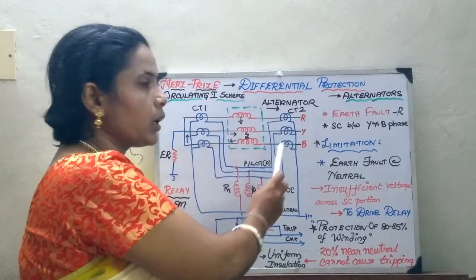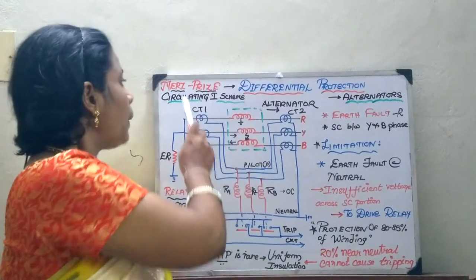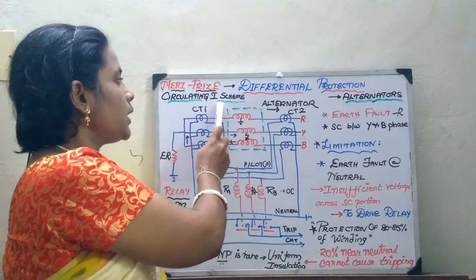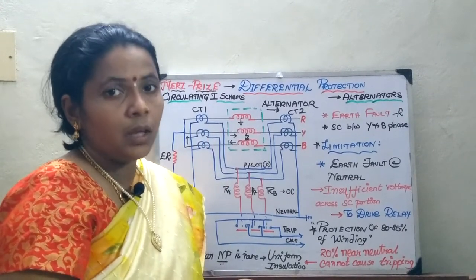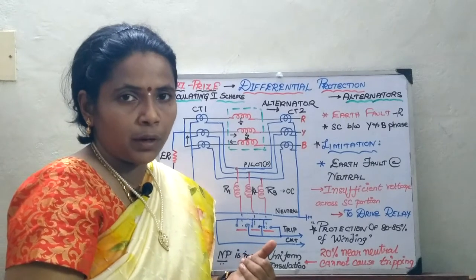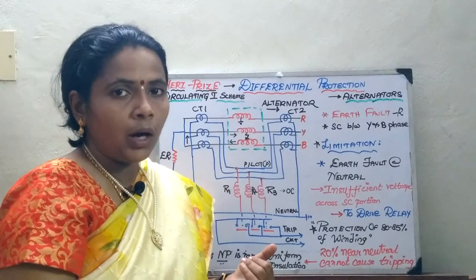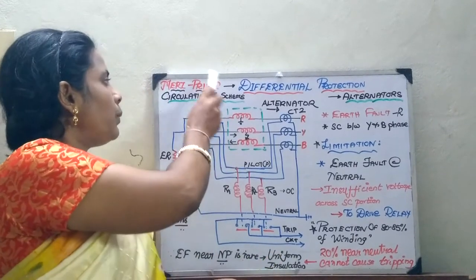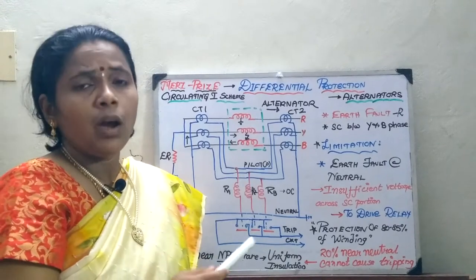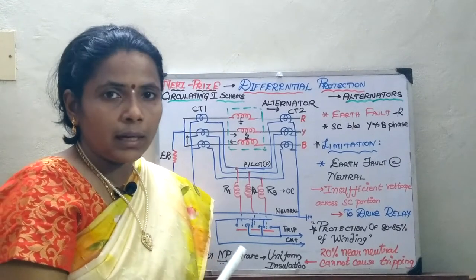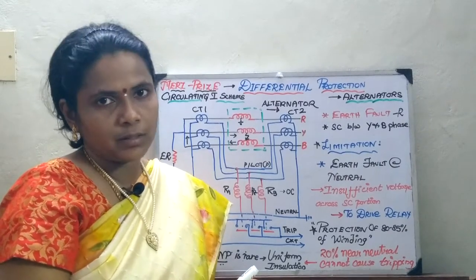Since the current circulates inside, this method is also called the Merz-Price circulating current scheme. The question can be asked in different ways — it can be referred to as differential protection of alternators for protection of stator windings, or as the percent Merz-Price circulating current scheme, or as the current differential protection for alternators.